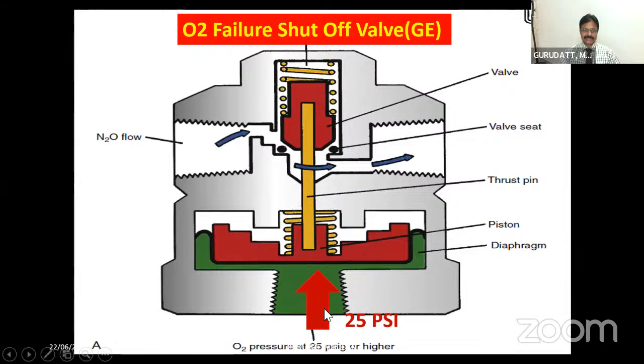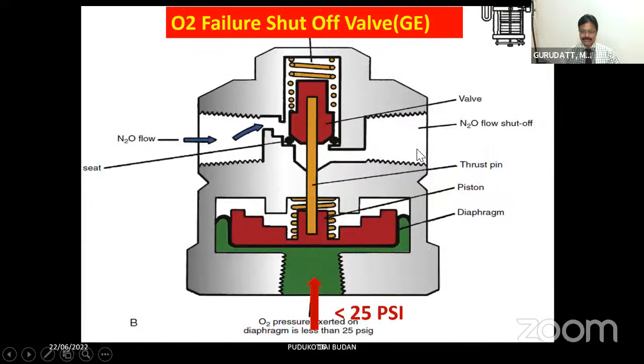So in the GE workstation, you can see here, as long as the oxygen pressure entering into this fail-safe valve is more than 25 psi, the thrust pin is going to push the valve away from the flow of nitrous oxide, and the nitrous oxide can easily flow out of this fail-safe valve. So once the pressure of the oxygen falls to less than 25 psig, the thrust pin will come down and totally close the valve. So once the valve is closed, there is no flow of nitrous oxide out of this fail-safe valve. So nitrous oxide flow is just cut off.